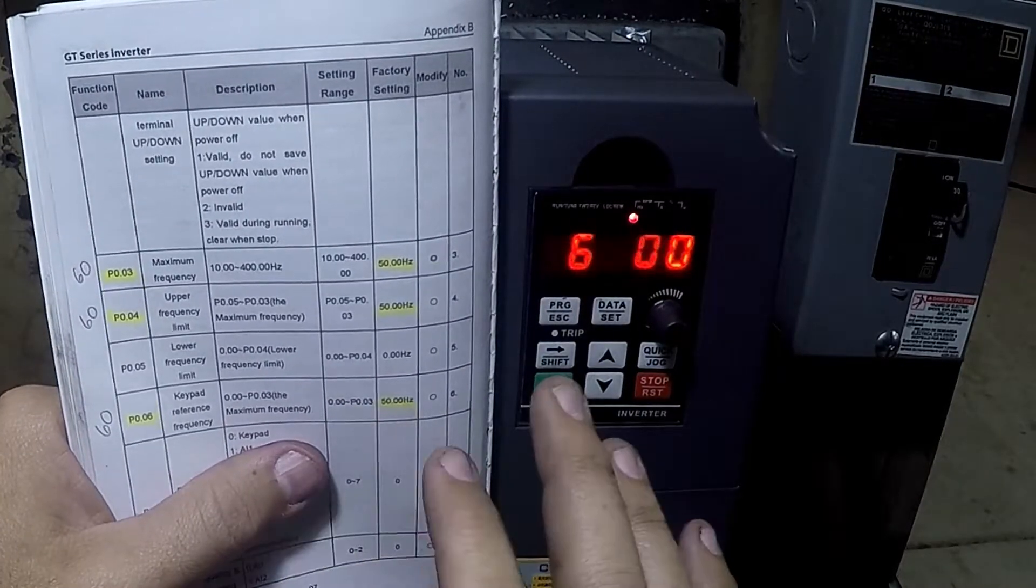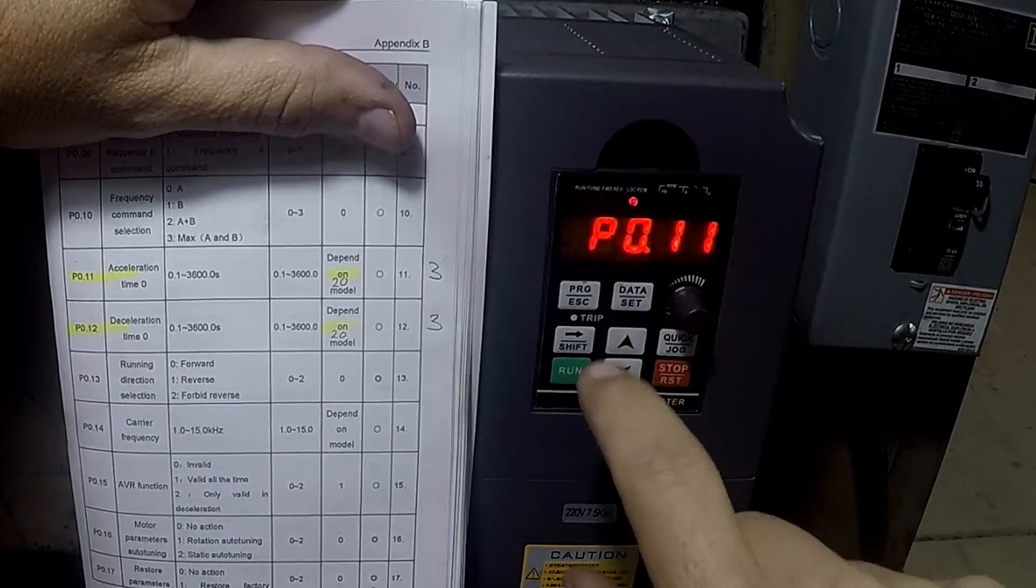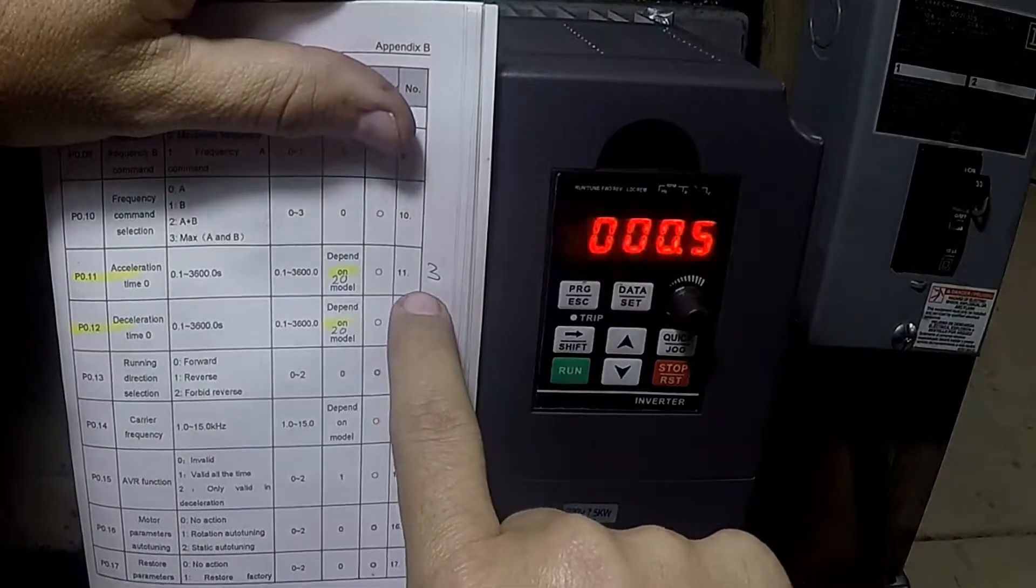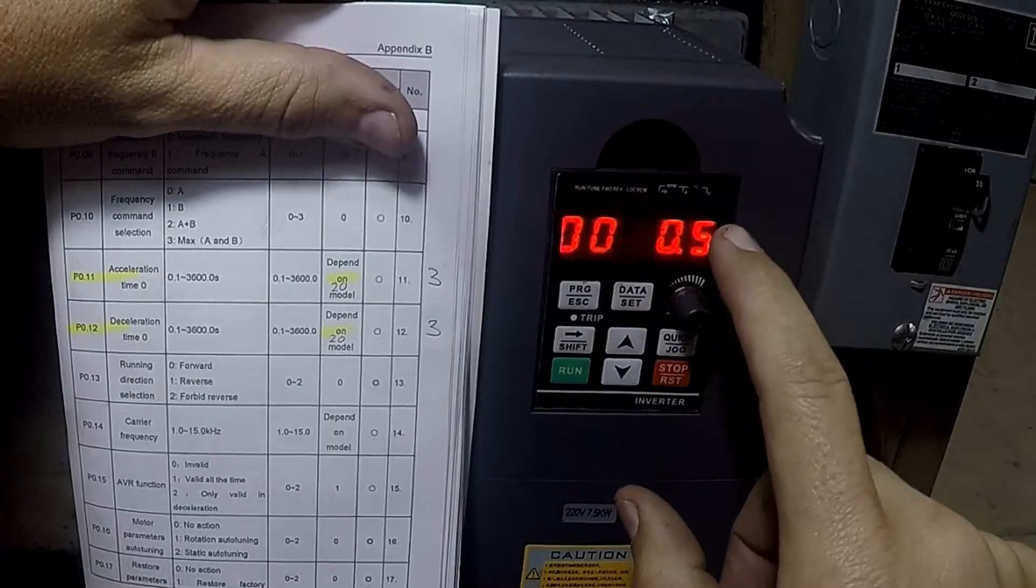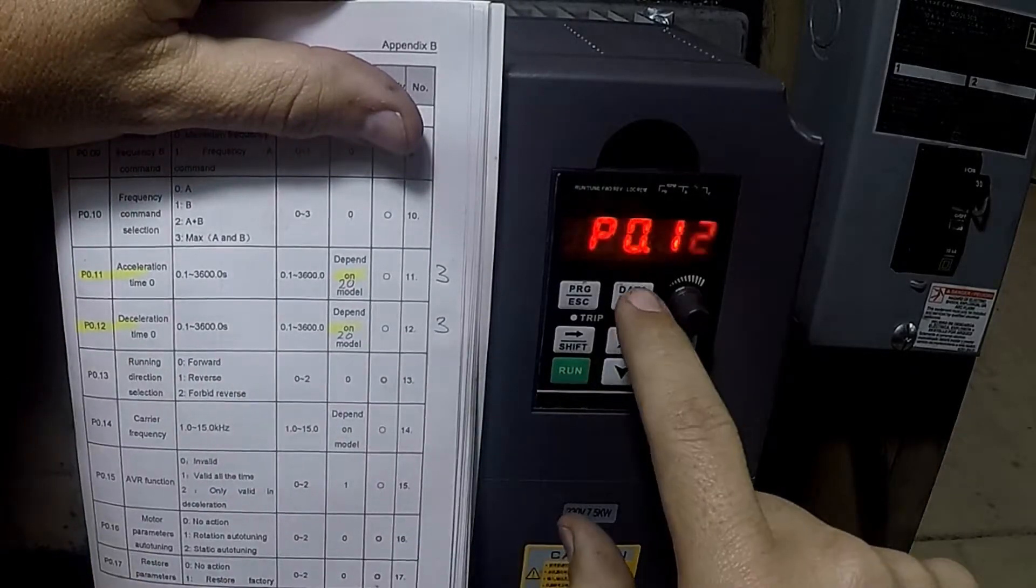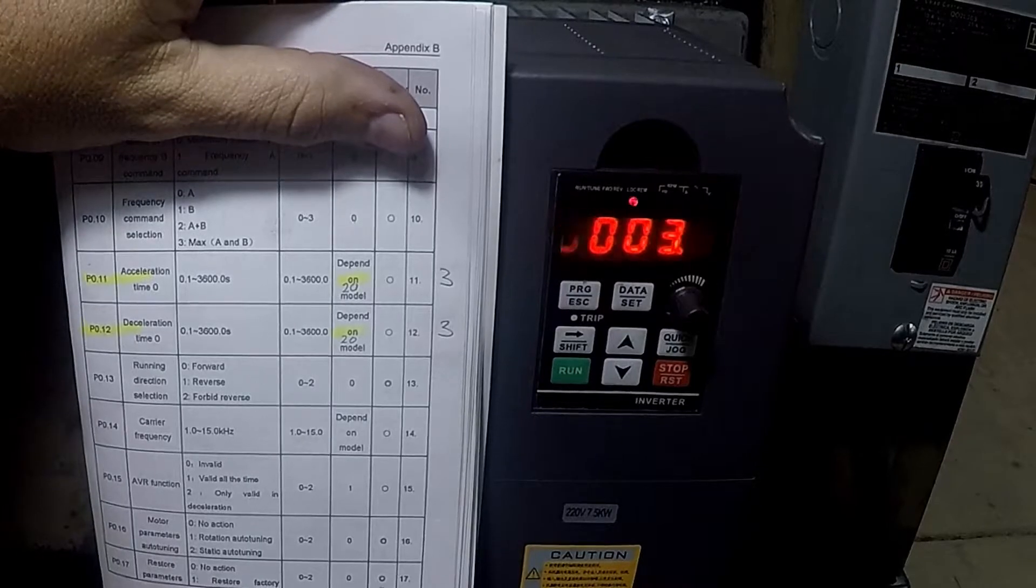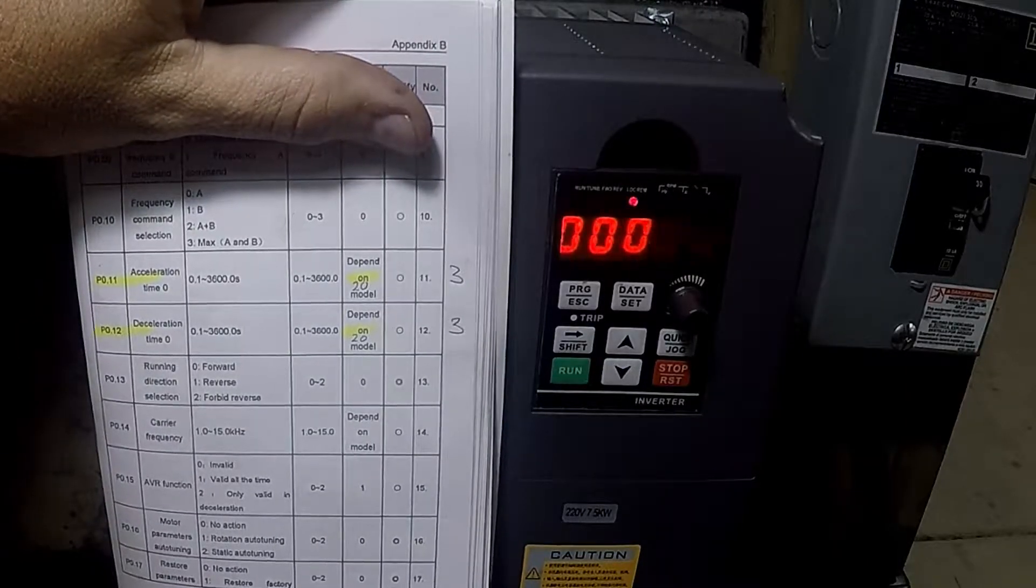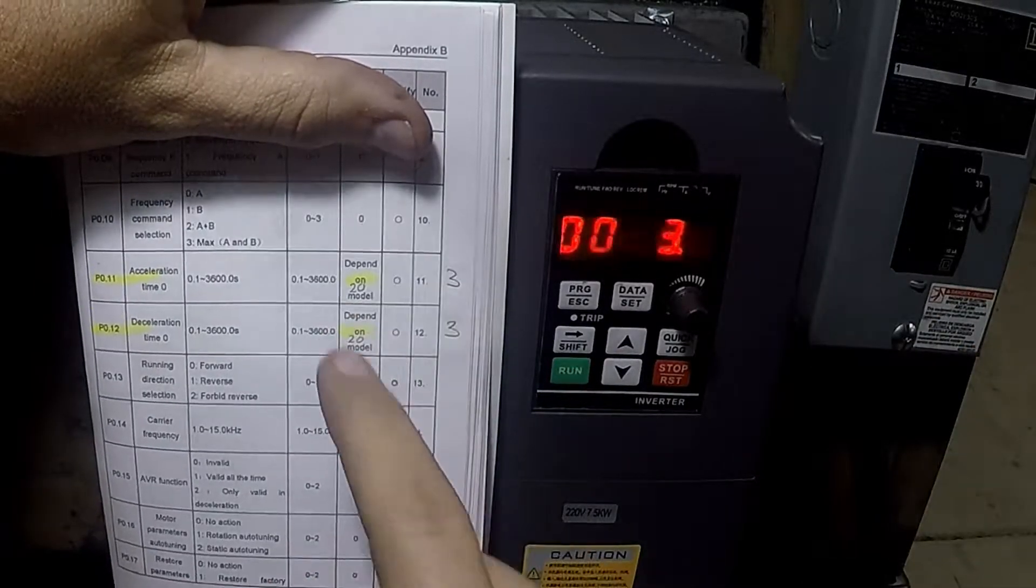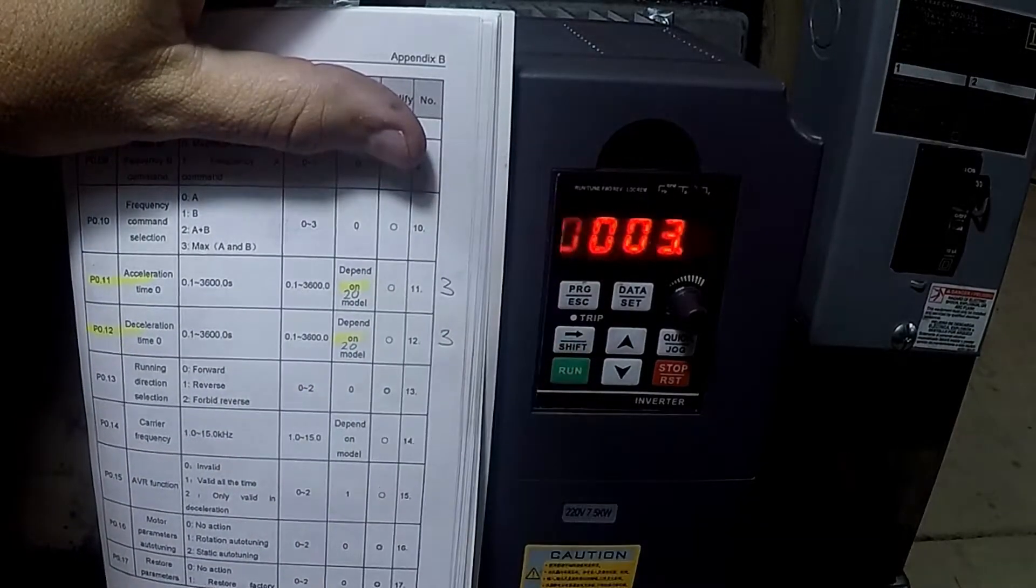The next one here is to go to P0-11. This is the one where I had three here before. I've set this to a half second so that the motor starts up a lot faster. The three second was okay, setting it to a half second is much nicer. The deceleration time P0-12 I've left at three seconds. The default on these were 20 seconds which is a really long time. I believe the Bridgeport had a similar issue where when you hit run it would literally go extremely slow, spin up taking 20 seconds to come up to full speed. So this is one thing if you're noticing that behavior, this is what you need to look for to actually fix that.